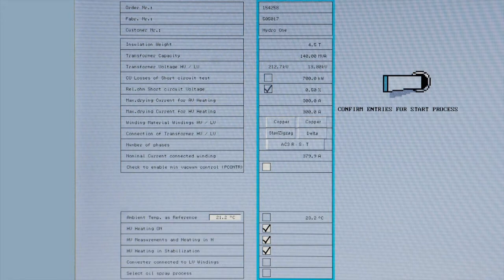HV heating on. Activating this feature allows one to heat the HV winding separately. If it is not activated, then the system will use average heating. HV measurement and heating in the heating stage. If this is not selected, then no HV measurements will be made during the measurement and during the heating stages. The HV measurements would then be made in the fine vacuum stages.